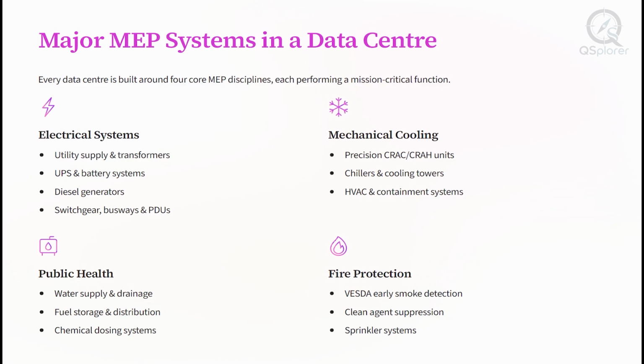Next comes the mechanical cooling system. Since servers produce a large amount of heat, precision cooling equipment such as CRAC and CRAH units, chillers, cooling towers, and containment systems maintain the required operating temperature. The third discipline is public health, which includes water supply, drainage, fuel storage for generators, and chemical dosing systems. Finally, fire protection is especially important because water-based suppression could damage expensive IT equipment. Therefore, data centers often use early smoke detection systems like VESDA, along with clean agent suppression systems that extinguish fires without harming electronic equipment. Together, these systems ensure safe, efficient, and reliable operations.